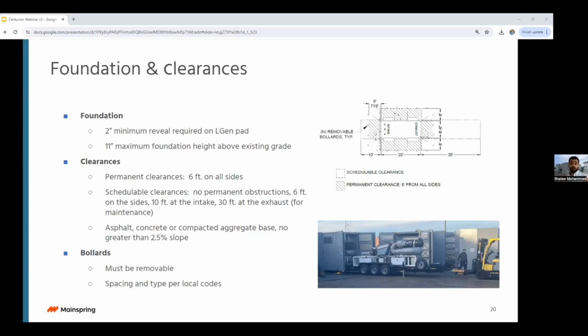We do, however, require 30 feet scheduled clearance on the exhaust end and 10 feet scheduled clearance on the intake end. The 30 feet scheduled clearance is because, sometimes, on major rare events, on major maintenance, we may pull the core out. As you can see in the lower right picture, pulling that core out requires some space. So you can definitely use the space for your day-to-day business. But when we pull that core out for major or rare events, then we would require that space. So again, it is scheduled clearance, not necessarily required clearance.